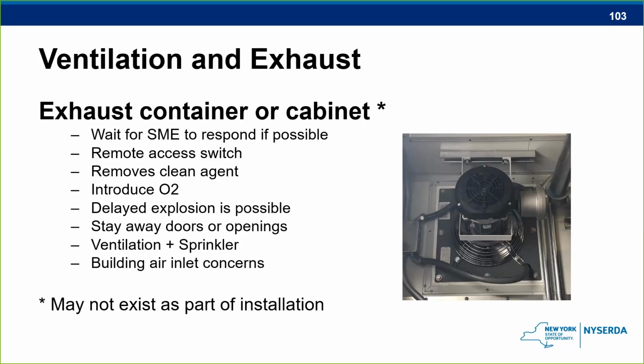In some situations, there are suppression agents called clean agents that are used in these lithium-ion installations. So the clean agent will come in there, and basically what it does is remove oxygen or react with the gases in there to make sure it doesn't go on fire. But when you remove that from the exhaust location, now you're removing the clean agent. So there are things that automatically come with clean agents already installed inside of them.